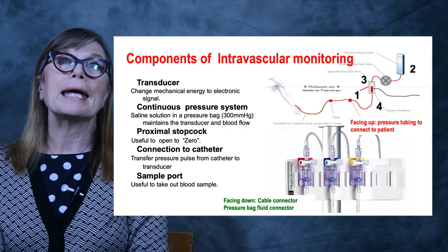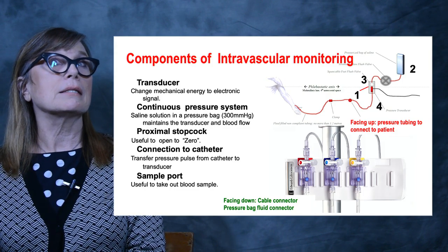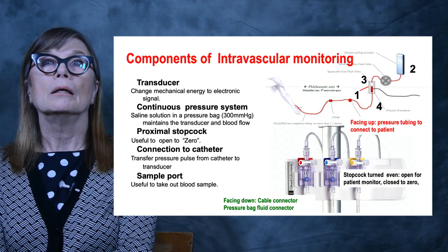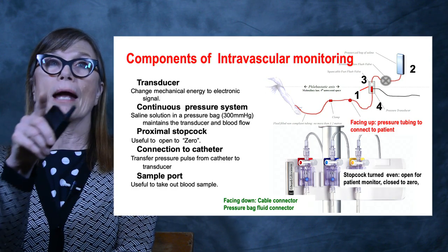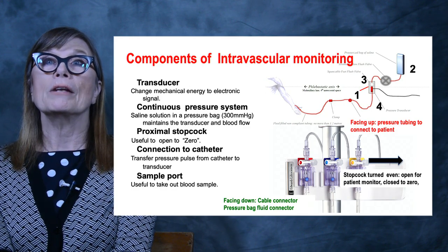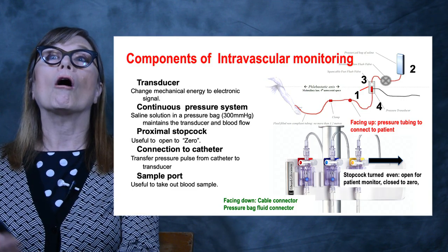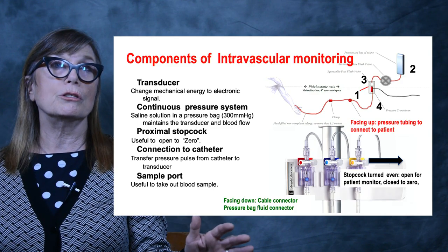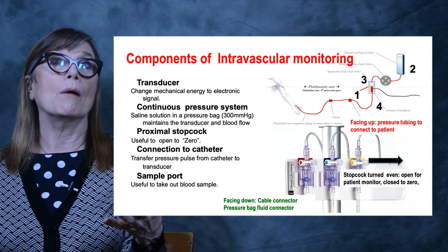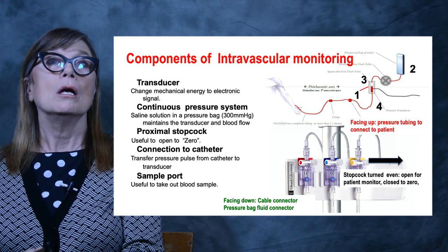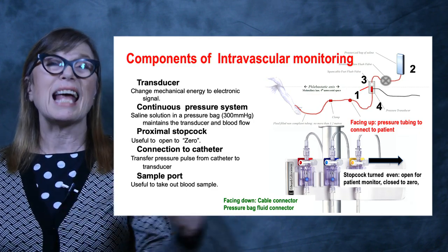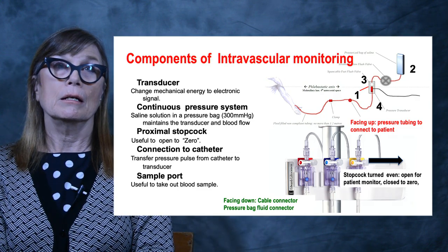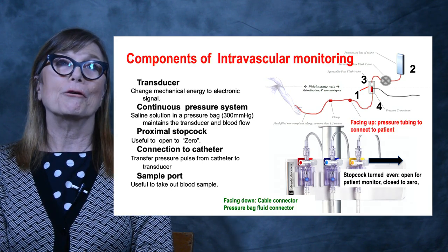And you also see a stopcock. Now, one of my colleagues asked me to remind you about the stopcock. When your stopcock is turned even, as it is right here, straight across, you are open to monitor from your patient to the transducer, and you are closed to zero, which means closed to allowing air to enter into the transducer. So in general, at all times, your stopcock should be turned even, because that's how you monitor your patient.